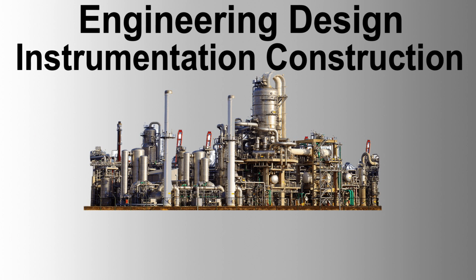Technical requirements. Loop testing, general requirements. Loop testing shall be performed to verify the correct installation and functionality of all instrument loops. This includes checking the continuity and integrity of wiring, as well as the correct operation of instruments and control systems. All instruments and control devices in the loop shall be properly calibrated before testing.